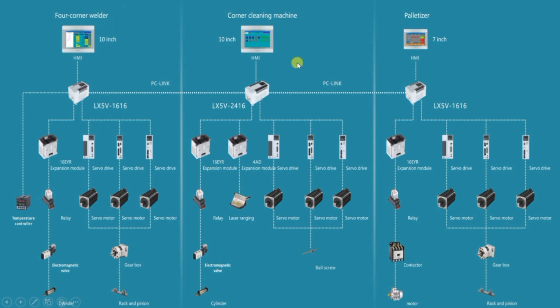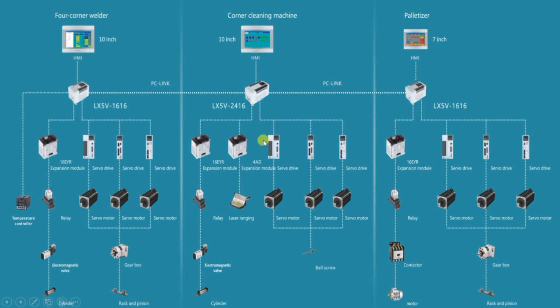For the corner cleaning machine, there is horizontal movement, vertical movement, and angular spindle movement — so there are three servo motors. There is also a laser ranging sensor, plus relay-solenoid valve-pneumatic cylinder combinations for clamping the door frames tightly during the cleaning, grinding, or cutting process. For the palletizer, it moves upward, downward, and horizontally in different directions, requiring servo motors and servo drives. This is the complete architecture of the production line.